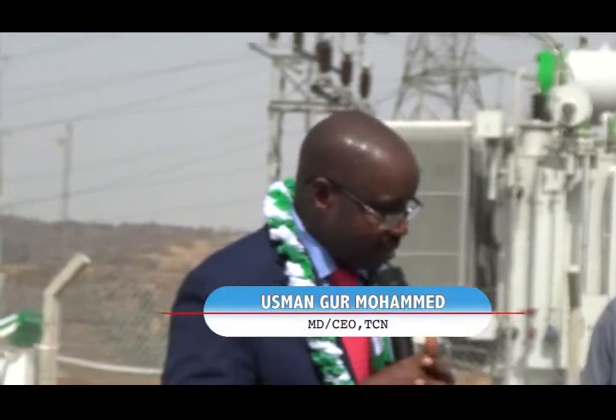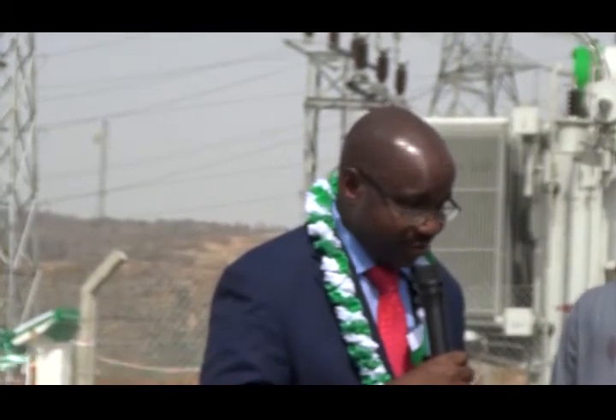We added it to the existing transformer capacity in Katampe. The existing capacity in Katampe was 120 megawatts; with this addition of 100 megawatts, the capacity of Katampe has increased to 220 megawatts. With that development, we have met the N-1 criteria here in Katampe, meaning if one transformer failed, the society would not feel it. That means the Abuja Disco will not lose electricity because one of them has failed.